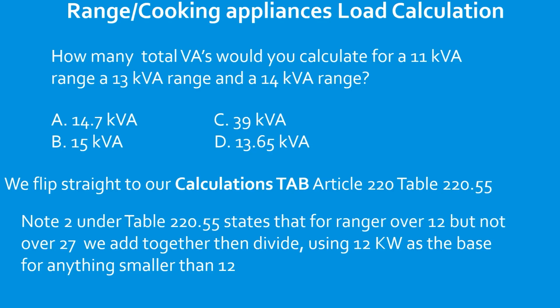Okay, so it sounds kind of tricky, but we're going to talk about it now. The only thing you have to watch out for with this type of question is any individual range, the minimum that it can be is 12 for this calculation. So you see our 11 kVA range, it has to be bumped up to 12 in order to do our math.